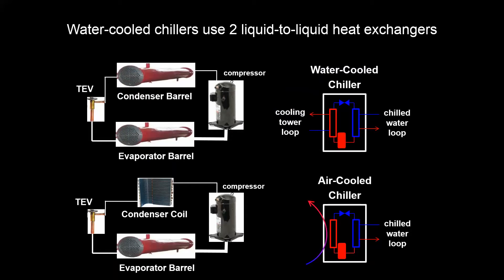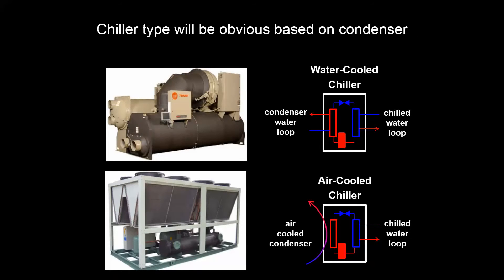With a water-cooled chiller, we're really just going from a condenser coil and evaporator barrel to two barrels. On the condenser side, you have a condenser loop that's running out to a cooling tower or a series of cooling towers. The chiller itself is going to be pretty easy to spot if this is the case — a water-cooled chiller should be inside, and you're going to see these two barrels. Whereas with an air-cooled chiller, you're going to have condenser fans and condenser coils, and it will be outside.